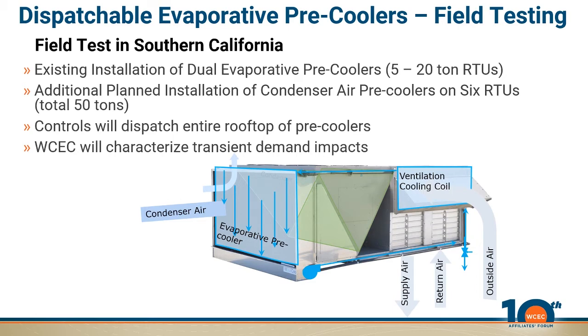What's your latest feel on effectiveness? It depends on the technology — that's what our ASHRAE standard is addressing. For the evaporative pre-coolers, we measured about four of them at around 70%, and one or two at around 35%. I was looking at a report that said 60%. We're doing some studies now on that. There's a bunch of them that got around 70. It's also relatively independent of wet bulb depression — it's been pretty constant across the different conditions we tested in the standard.